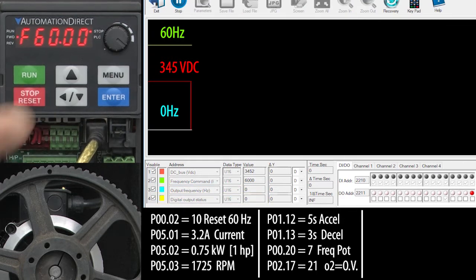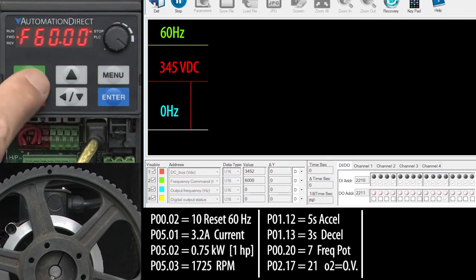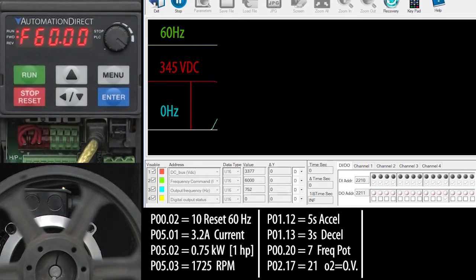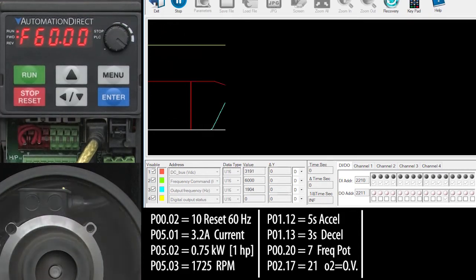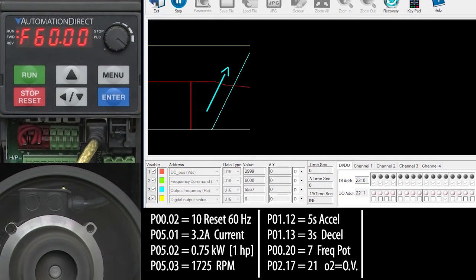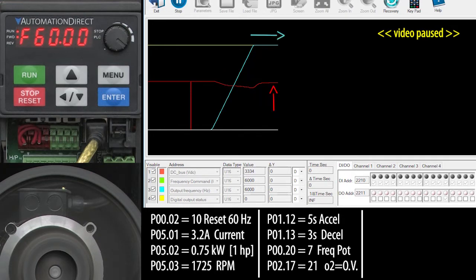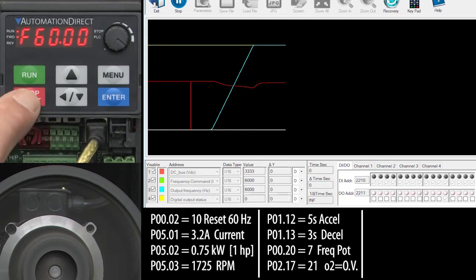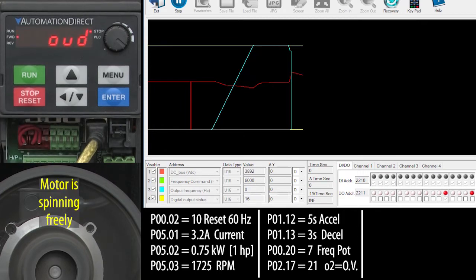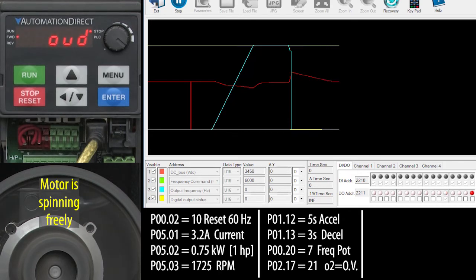I'll reset the overvoltage fault and hit run to do the exact same test so we can see it on the scope. I'll wait for it to ramp up to speed and for the DC bus to settle out. You can see the DC bus voltage drooped while the motor was accelerating, but once it got to speed the DC bus leveled off because the motor doesn't need as much energy just to maintain the motor's speed.